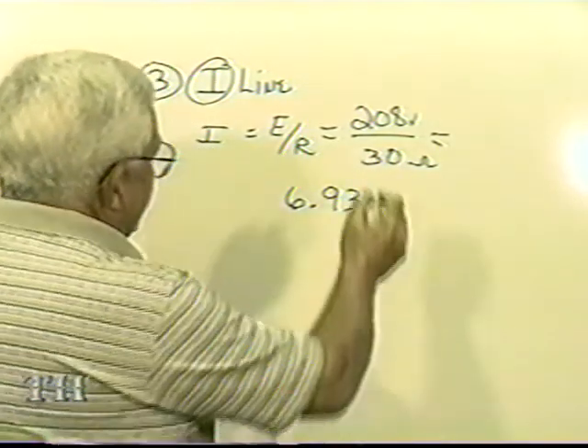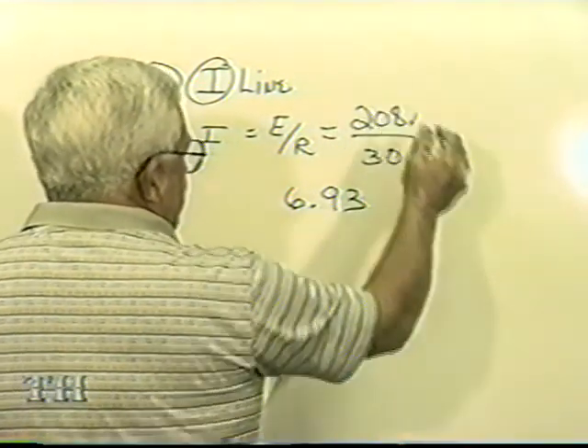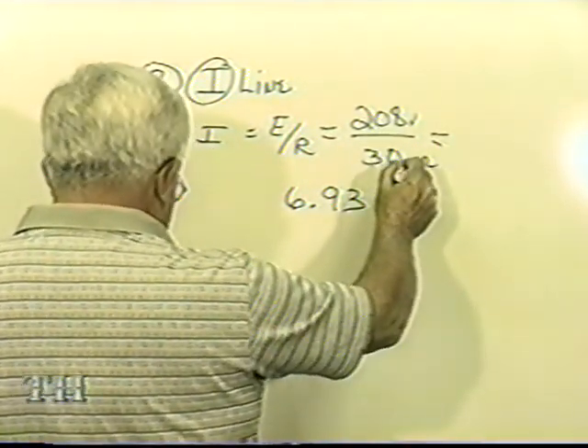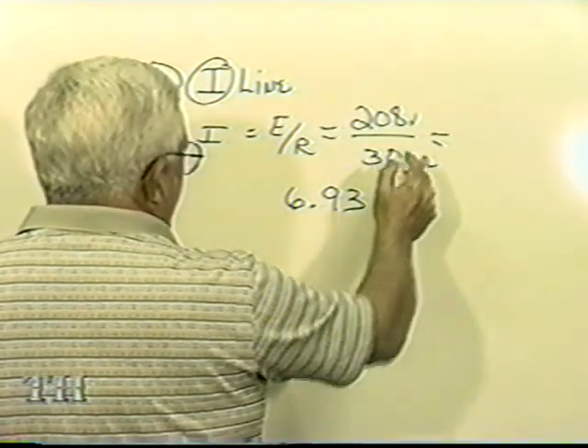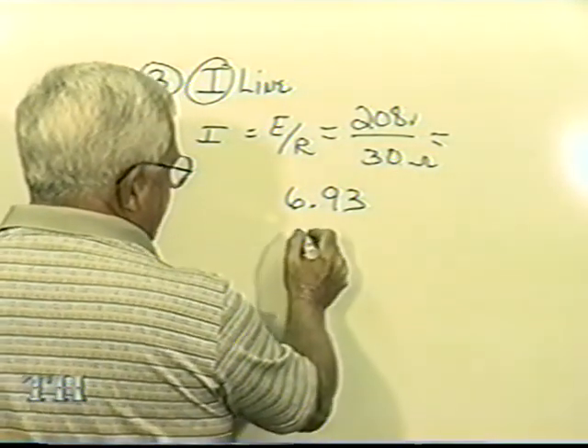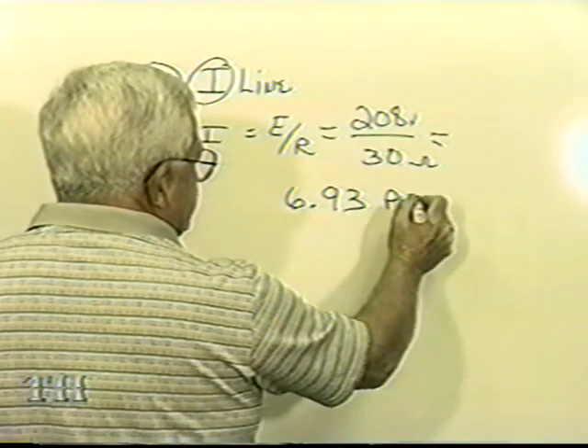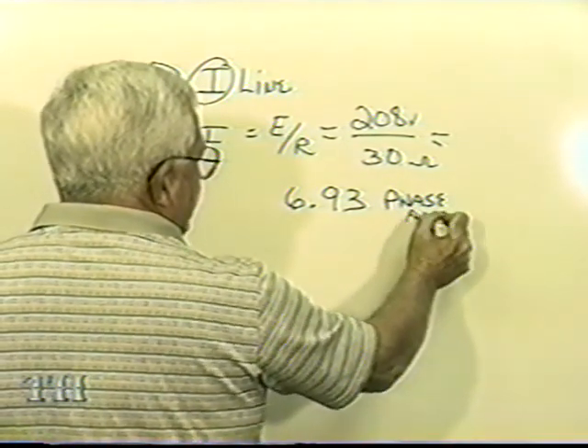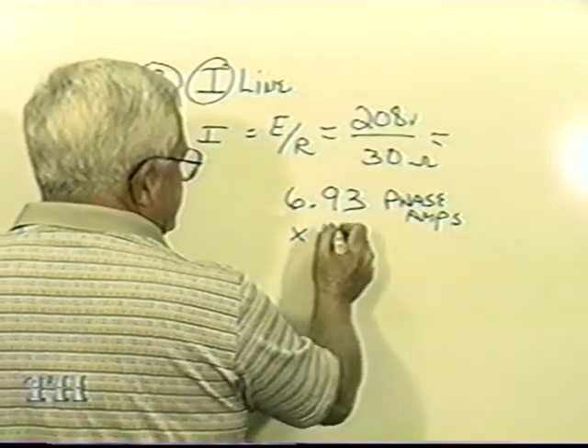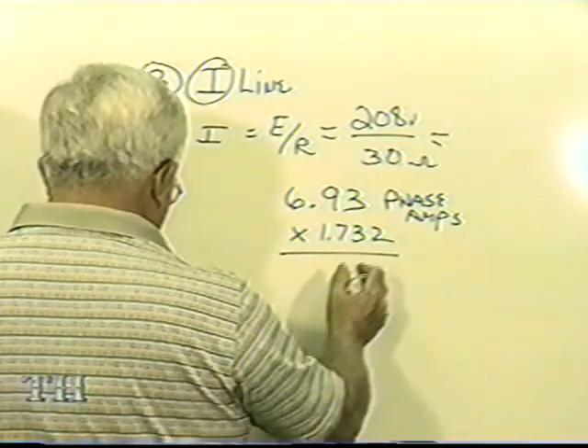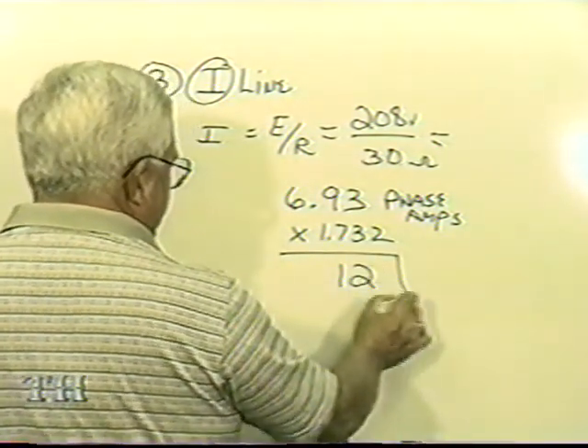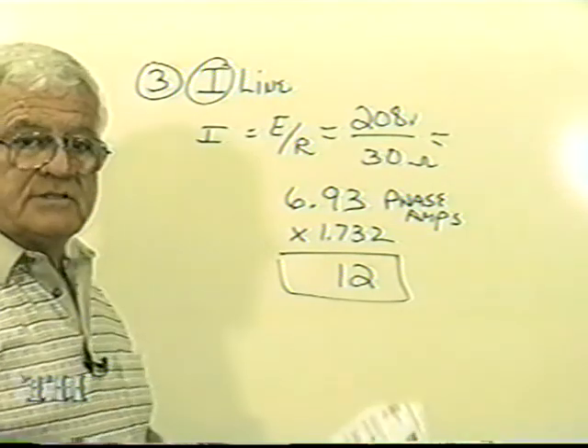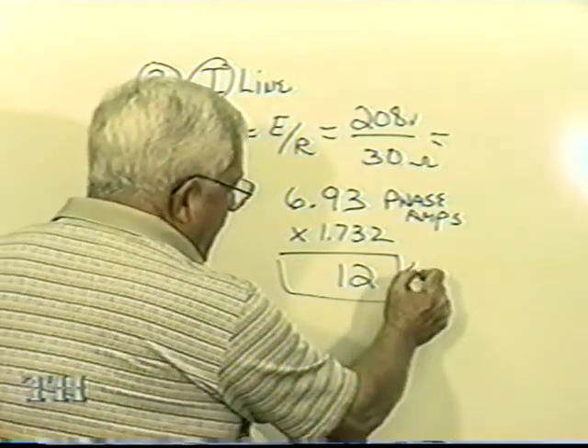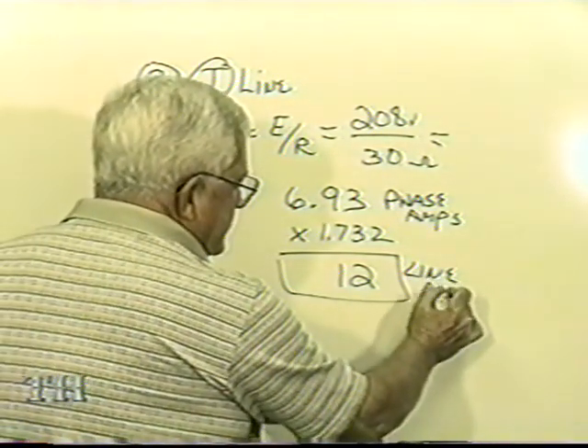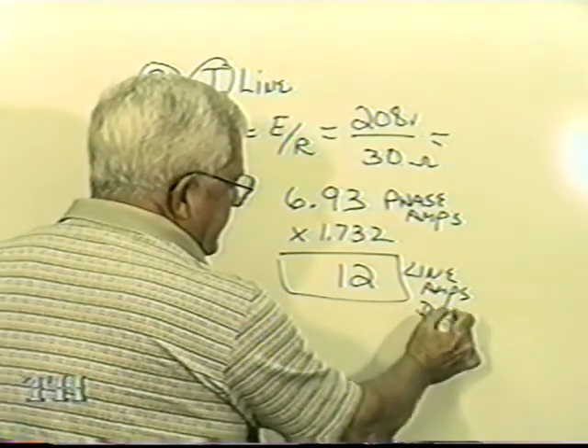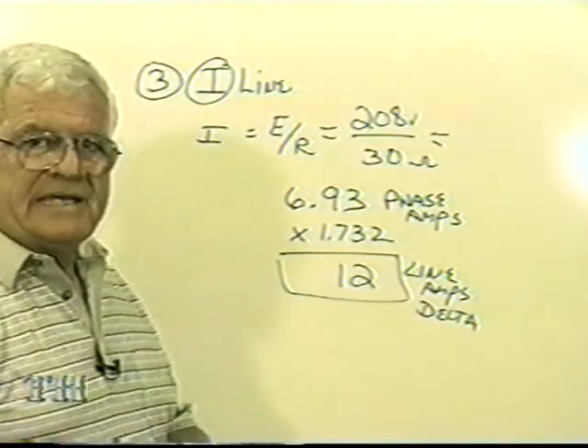But see, this is phase. This is the phase voltage and the phase resistance. And they want to know line in a delta. So I would have to take the phase amps in a delta times 1.732. In the line current, the correct answer to number 3 is 12 amps. This is your line amps delta. And see, that one's easy to miss.